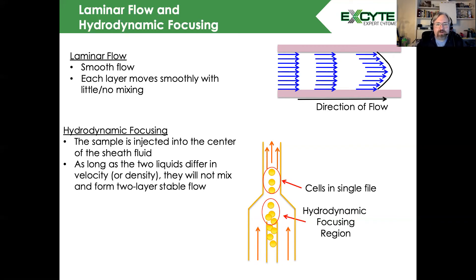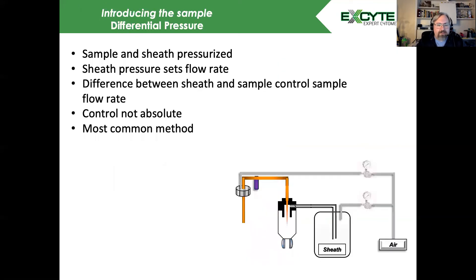There's a couple of ways we can generate this. The most common is a differential pressure system. Here we have our sheath fluid and an air compressor. You'll see we have two different valves that we're going to adjust. The first one sets the sheath fluid pressure, and we see the sheath fluid running here into our flow cell.